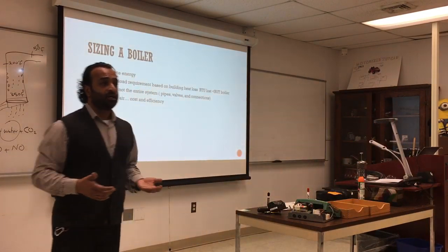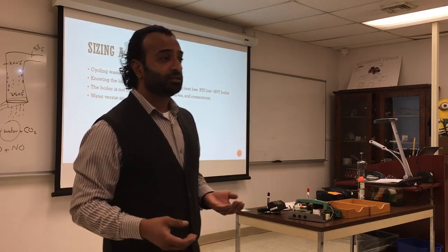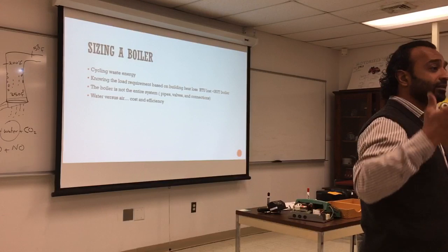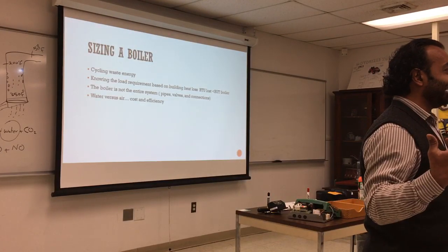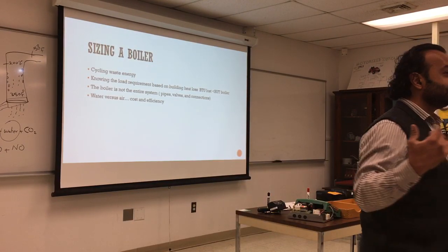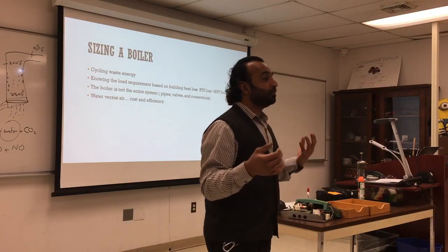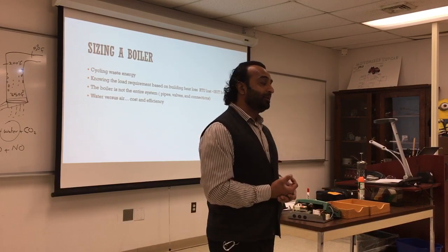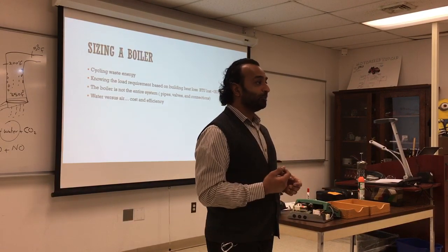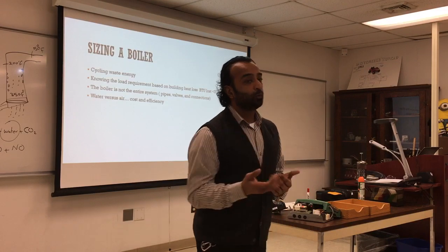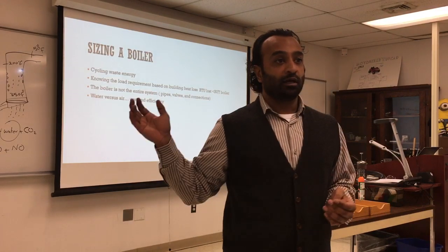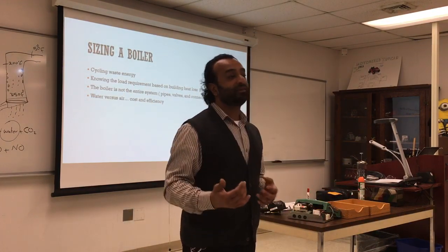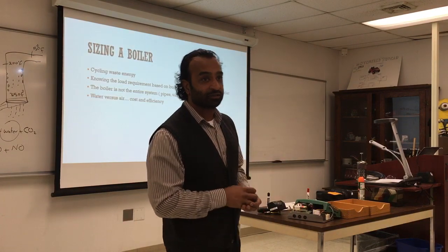The other thing is, how fast do you feel the heat? Which is faster, water or air? Air. You turn on the furnace, you feel the hot air because we are surrounded by air, not by water. So air is touching you faster, so you feel hotter faster. That's one thing people like about forced air. It's very quick. You turn it on, within 2 minutes the room is warm. Meanwhile, with water, you have to wait until the boiler heats the water, it comes to the radiator and starts heating the room. It takes at least 15 to 20 minutes to feel that, to stabilize.